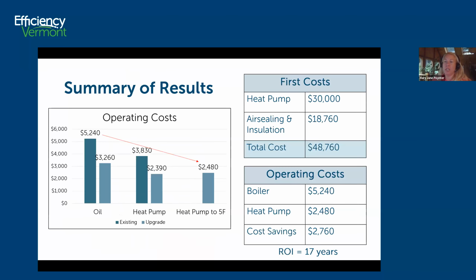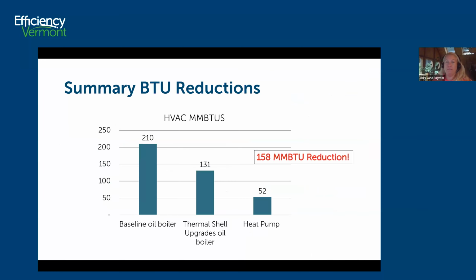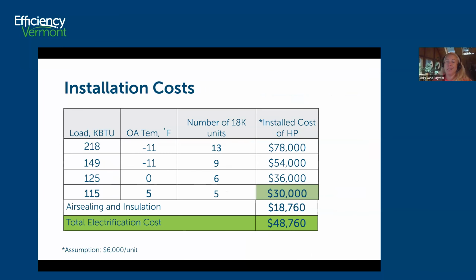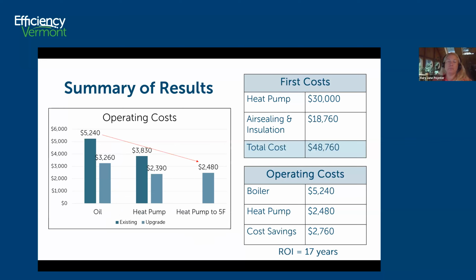So here's the operating cost versus the first costs. We started out with an operating cost of $5,240 with just the oil. If you were to get rid of all of the oil except for 1%, and put in heat pumps, you're looking at savings in operating costs going down to $3,260. But remember that first cost was $78,000. So you're saving about $2,000, but you're spending $78,000.